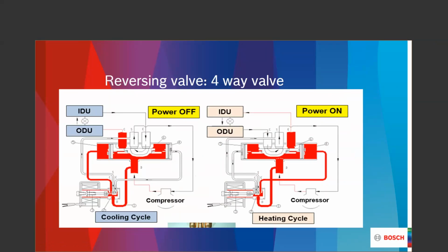This center port is going to allow us the switching mechanism from whether we are in the cooling cycle or the heating cycle. We're moving that valve over there, like we said a while ago, with pressure differential. Remember that if I have a switching mechanism and it's supposed to be switched, there shouldn't be any temperature differential between these two lines. They are basically the same pipe. But if I've got some problems in here and I didn't switch all the way, then there's going to be some temperature differential between what's going on and what should be going on.